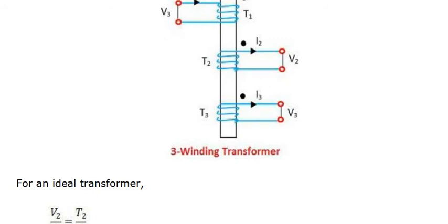First, tertiary winding is used to supply station auxiliaries, for example lights, fans, pumps, at a voltage different from those of primary and secondary winding. Second purpose, synchronous capacitor or static high voltage capacitor are connected across the delta connected output of tertiary winding for reactive power injection into the system.